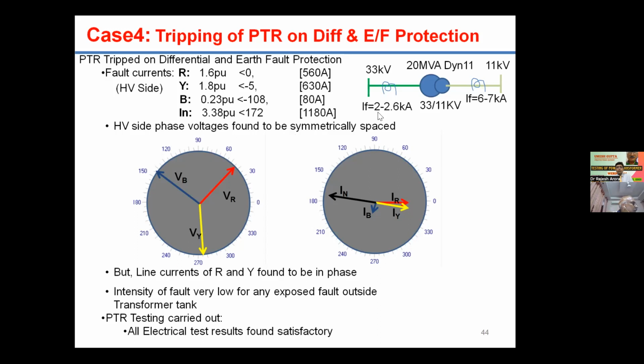Now we compared what the voltage profile was at that time. We captured this voltage profile from the DR of my incoming line. We found that all the phases of voltage R, Y, B are symmetrical, at 120 degrees apart. But the line currents of the transformer in R and Y phase are in almost the same phase, close to zero, and the neutral current is exactly opposite and the sum of R and Y phase.